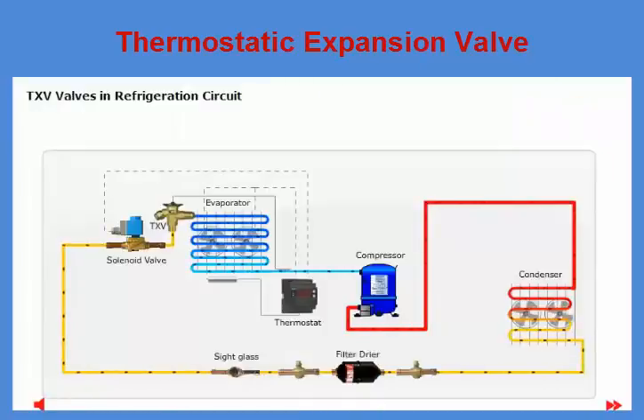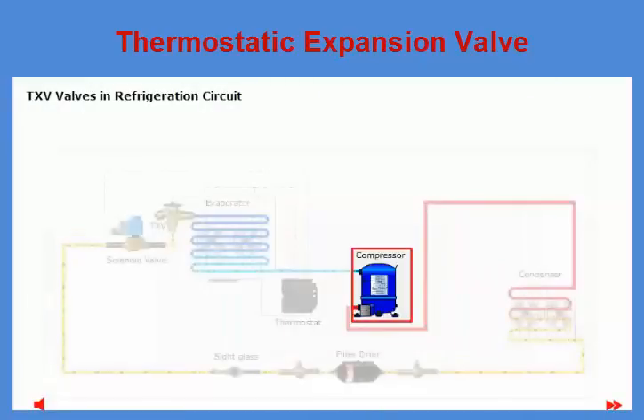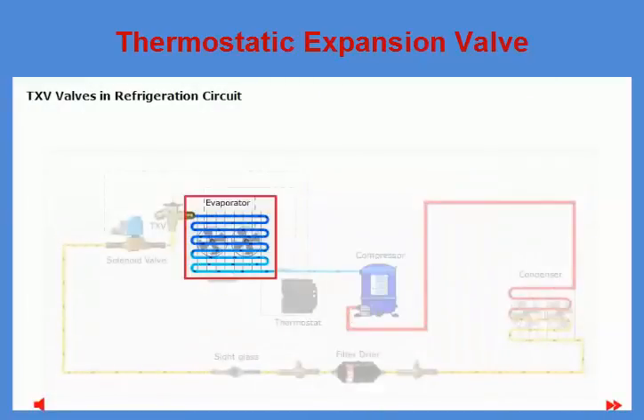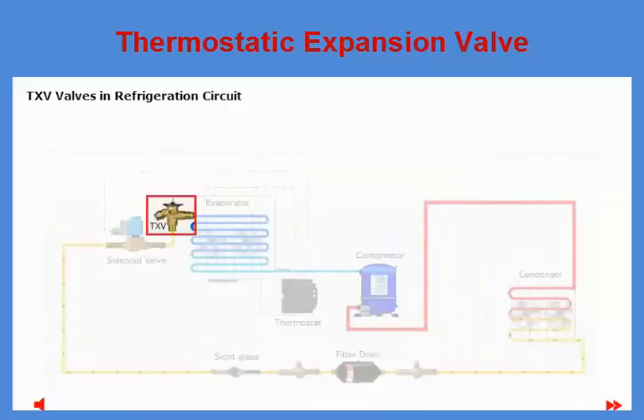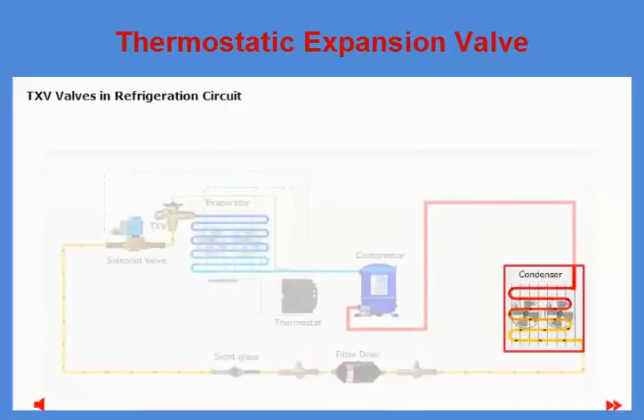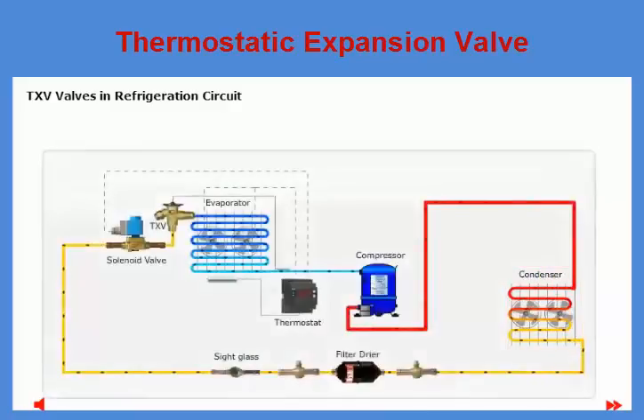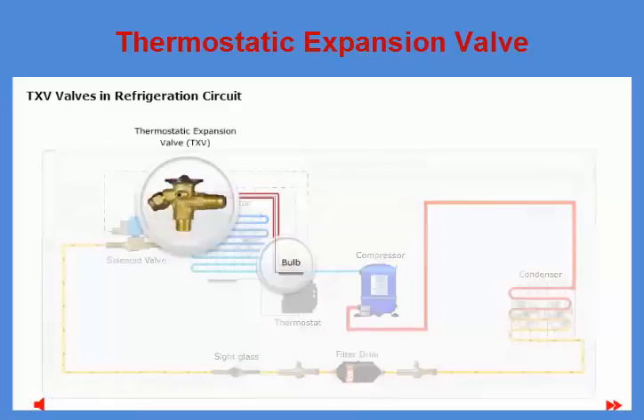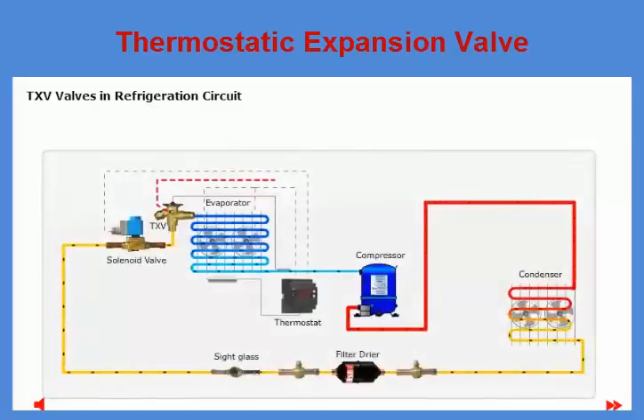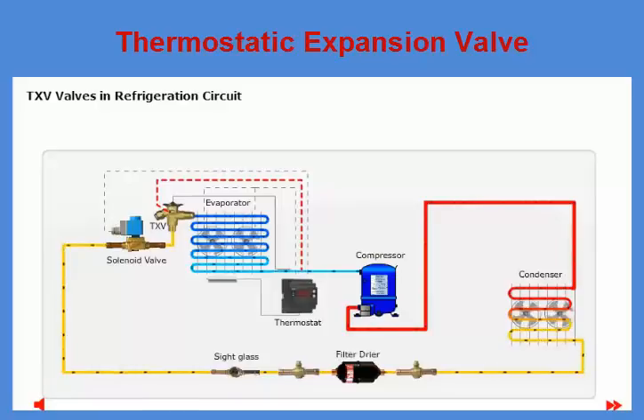Here you can see a basic refrigeration system with a compressor, evaporator, thermostatic expansion valve or TXV, and condenser as the main components. The thermostatic expansion valve is mounted in front of the evaporator, with the bulb and an external equalizing line mounted on the suction line just after the evaporator.